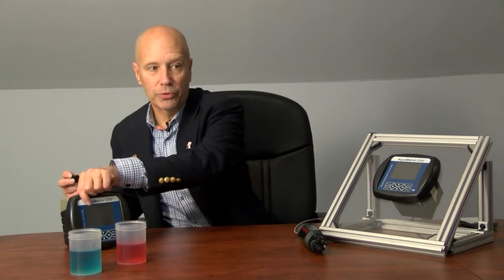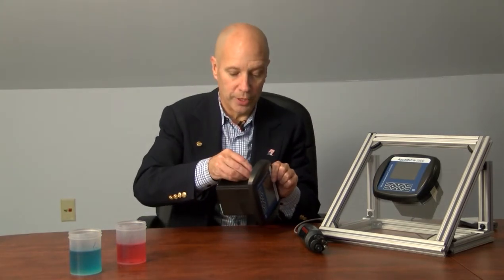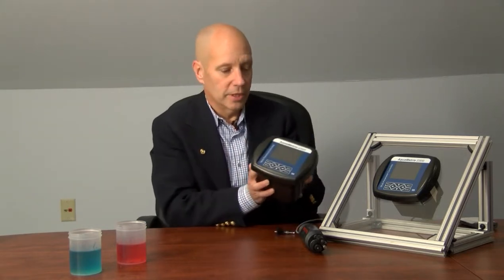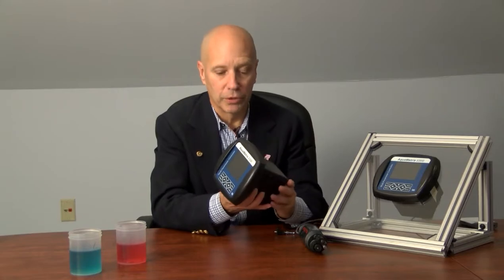A note first on mounting. The 2300 was designed to make panel mounting easy. To that end, you will find 2 mounting blocks on both sides of the unit. To mount the 2300, simply unscrew the mounting screw, slide out the mounting hardware, insert the plastic mounting pieces into the track, and tighten them against the back of the panel with the mounting screw. If you are mounting the 2300 on a surface, then you will want the wall mounting enclosure, also available from AquaMetrix.